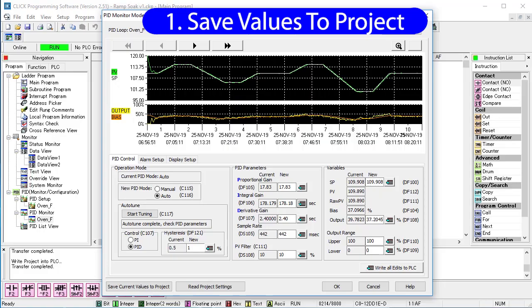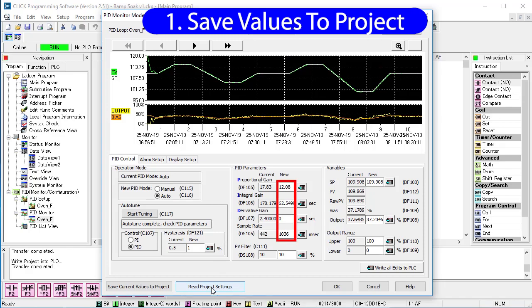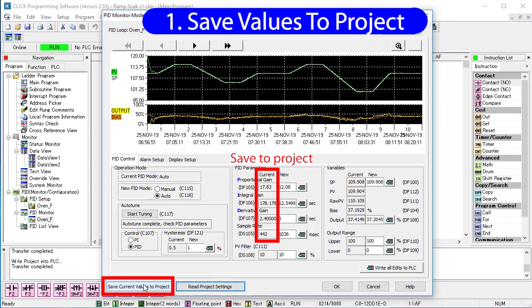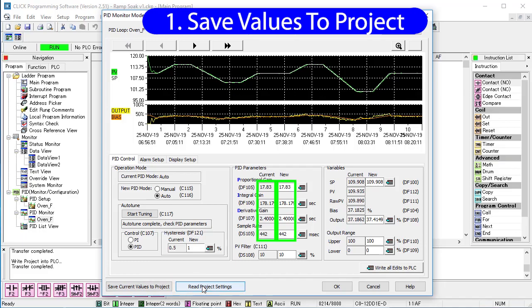Once you have your tuning coefficients the way you want them in the PLC, don't forget to hit this button to copy them back into the project so you can save them with the project. For example, if I hit read from project, I see the saved project values are not what is currently in the PLC. If I hit save current PLC values to the project, then read the project values, we see they are now the same.